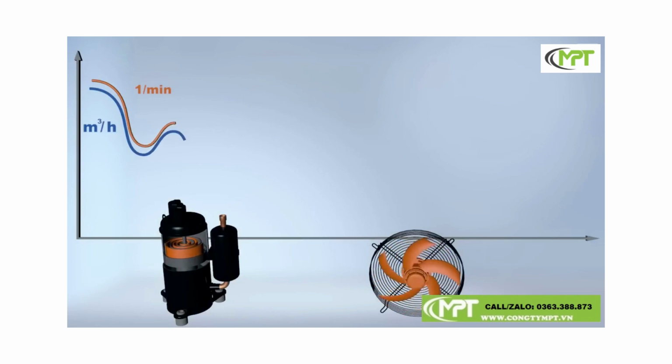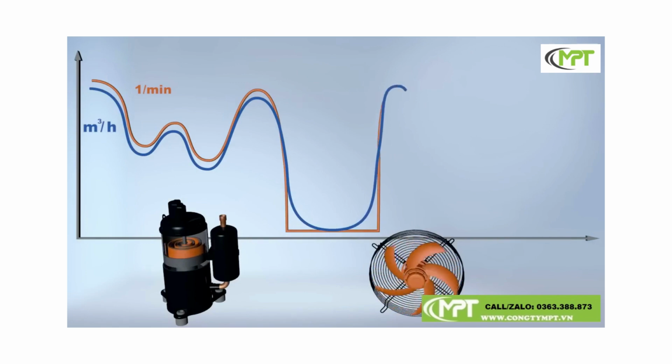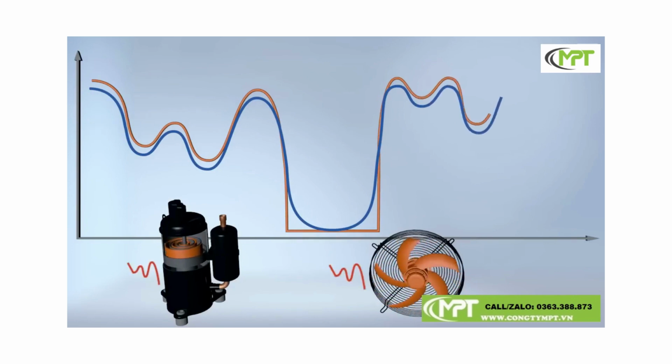smaller versions of the dry point RA Eco switch the refrigerant compressor on and off to accommodate variations in the drying requirements. After reaching a certain system size, the drying performance is controlled by changing the frequency of the compressor and thus even more finely adjusted to the volume flow. Larger dryers adapt both the speeds of the compressor and the fan to match the volume flow.